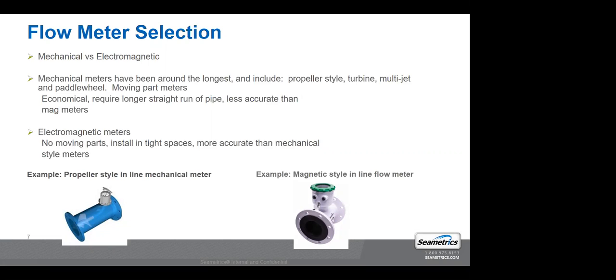And we see a picture of an example of a propeller style meter down in the left-hand corner. You can see that meter in different configurations. That meter's been around since the 1950s, and I don't think the design has really changed much since then. That's a mechanical propeller meter. Other types of mechanical meters are a turbine, multi-jet, paddle wheel. Again, these are moving parts meters. They used to cost quite a bit less upfront to purchase, not so much anymore.